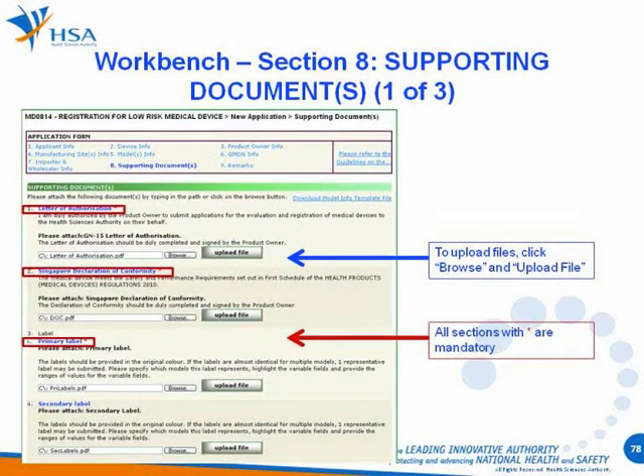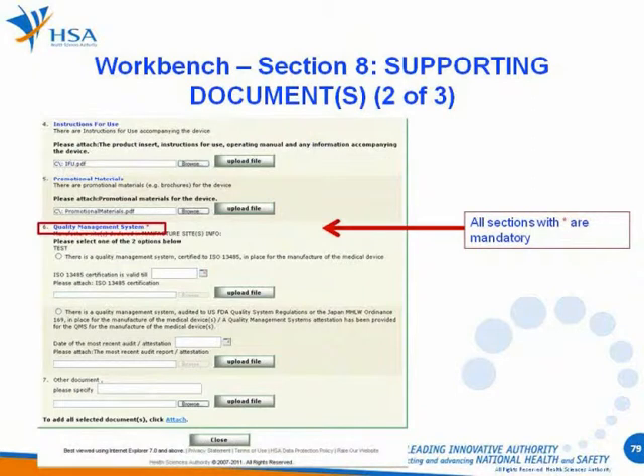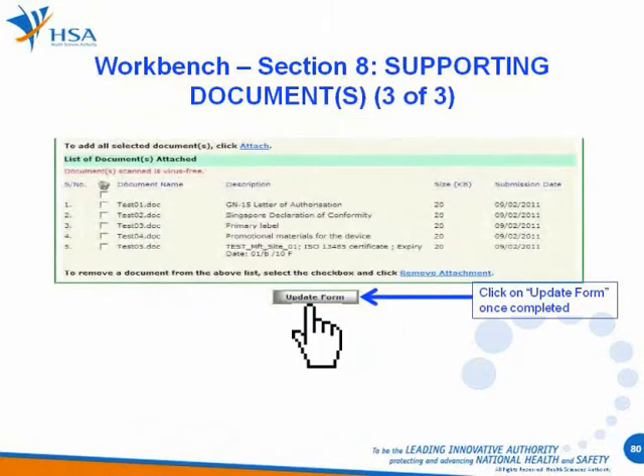The supporting documents are attached by browsing the local storage devices for the documents using the Browse button, then click the Upload File button to attach these documents. All sections with asterisks are considered mandatory, so you would need to include the Letter of Authorization, a Singapore Declaration of Conformity, and the Primary Label. This also includes the Quality Management System Certificate for the Manufacturing Site declared in the Manufacturer Site Information section. Your cooperation to provide the information will greatly facilitate the review process. Click on Update Form once completed.